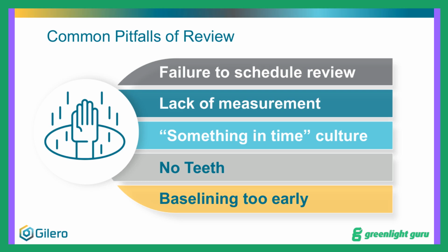Next, lack of measurement. If you're not measuring anything, it's very hard to make decisions based on anything other than gut feel. Design review is a good opportunity to compare progress to schedule and evaluate if the project is appropriately resourced given the project schedule. Further, where testing data is available, use this to evaluate how well the design is meeting the requirements well prior to attempting your design verification testing, so the device can be improved prior to that, as well as prior to moving to things like production tooling.